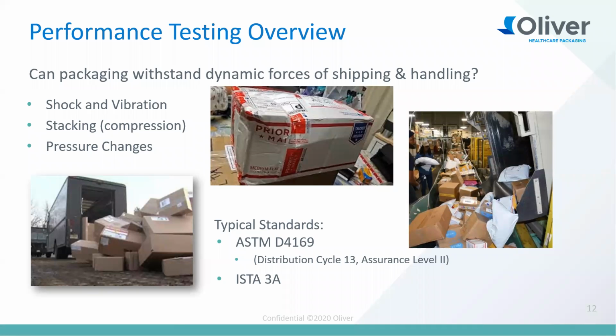And again, there are obviously standards around this. Jeremy, because you're the guru on the standards, do you want to take us through them as well? Yeah, Tommy. So we have a couple of standards listed here. We have ASTM D4169 and ISTA 3A, and these are both recognized in 11607 Part 1. They are very commonly used around the world. In my experience, D4169 is starting to trend up as being more commonly used. However, ISTA is very common as well. What we're going to be showing you in a video on the next slide is ASTM D4169 and some of the steps that we've talked about. The distribution cycle listed here is distribution cycle 13. If you look inside of that standard, there are multiple distribution cycles in there. And DC 13 is the one that is selected for medical devices throughout the industry.